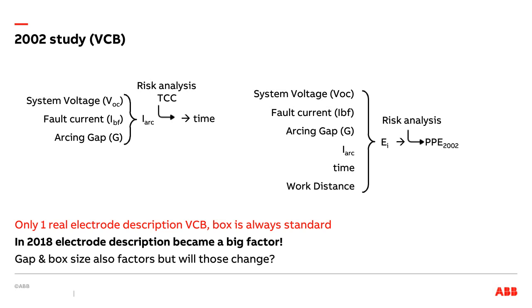Similarly, do I have multiple topologies, i.e., do I consider this with motors on, motors off, the emergency generator connected, emergency generator not connected, etc.? All kind of goes into that risk analysis when you're calculating current, which time current do you use, etc. And that develops a time. That time is then used again with the system voltage, fault current, arcing gap, blah, blah, blah, to develop energy. Now you have an incident energy number. Again, you go through a risk analysis process and you develop a recommendation for PPE, typically higher than the incident energy that you've calculated. But again, in the old study, there was only one electrode configuration, one electrode environment.